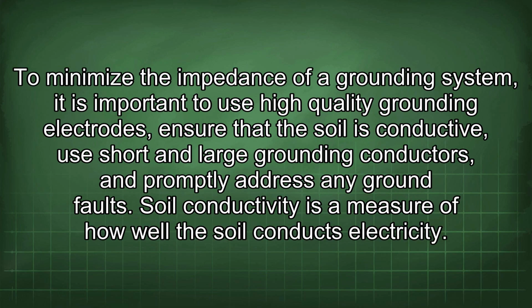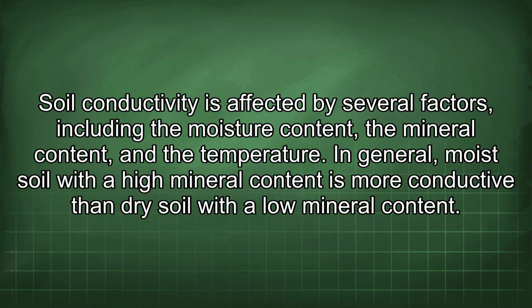To minimize the impedance of a grounding system, it is important to use high-quality grounding electrodes, ensure that the soil is conductive, use short and large grounding conductors, and promptly address any ground faults. Soil conductivity is a measure of how well the soil conducts electricity. Soil conductivity is affected by several factors, including the moisture content, the mineral content, and the temperature. In general, moist soil with a high mineral content is more conductive than dry soil with a low mineral content.